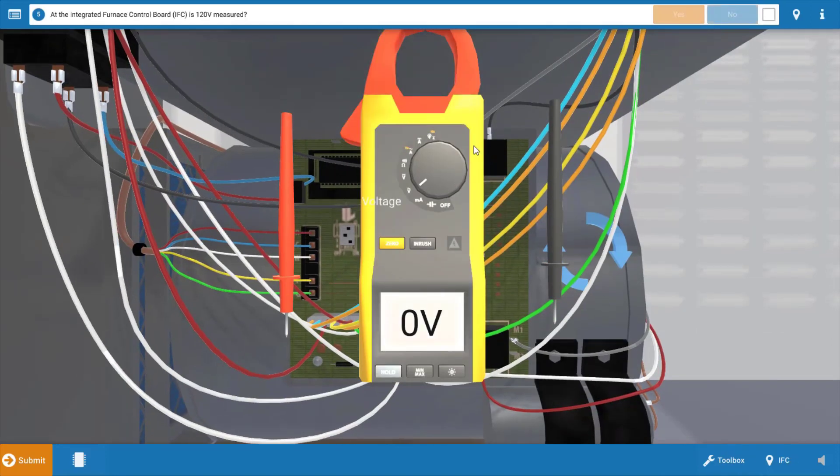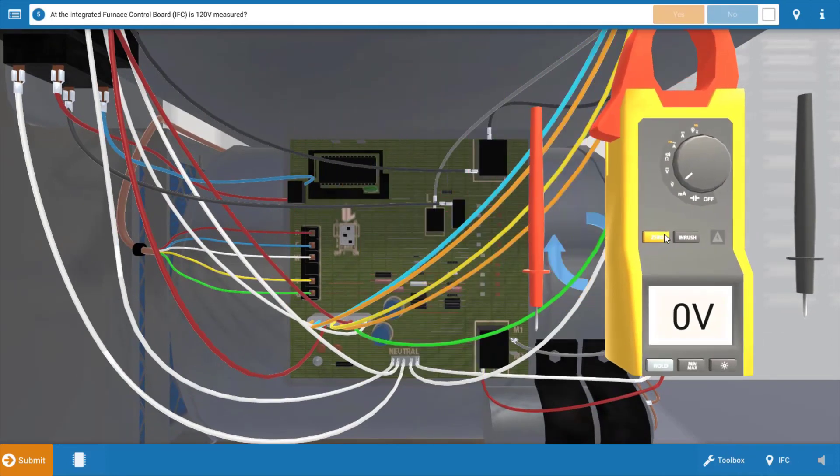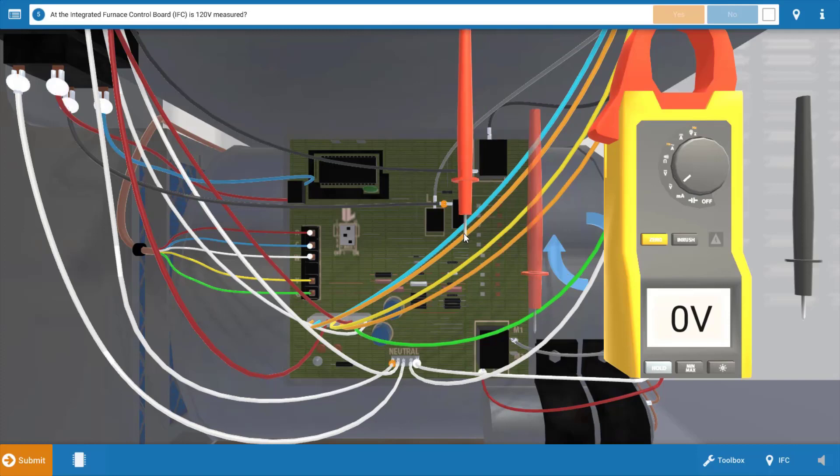Now our next step is to see if 120 volts is being received at the integrated furnace control or the IFC. Although we taped the door switch in, it's possible that its contacts are faulty or it's possible we don't have main power due to a breaker being tripped or a service switch being in the off position. So first we're going to measure for 120 volts at the line voltage inputs on the IFC.